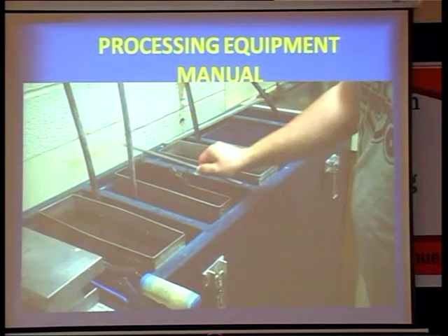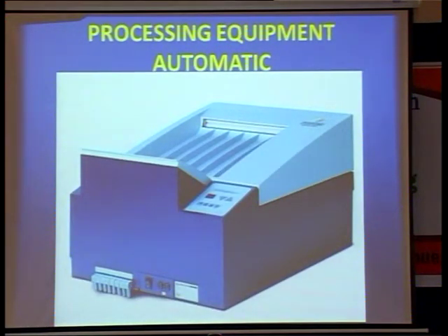Next one. This is the manual procedure we have told: developer, rinser, fixer and washing. This is the automatic process. This is a little easier because after rinsing and everything, you put it in the box and it comes out as a film. It is easy because with the chemicals there are two possibilities of discomfort. If a person is allergic, or has rhinitis or sinusitis, the chemical's irritants will produce sneezing and everything. To avoid this for medical people, that is the doctor's assistants who are working there, the processing by the automatic unit is the ideal one at present.